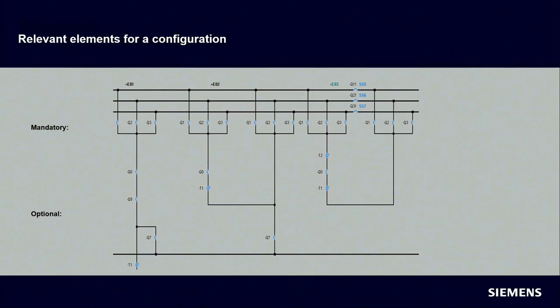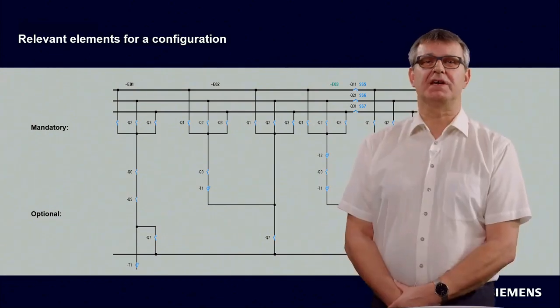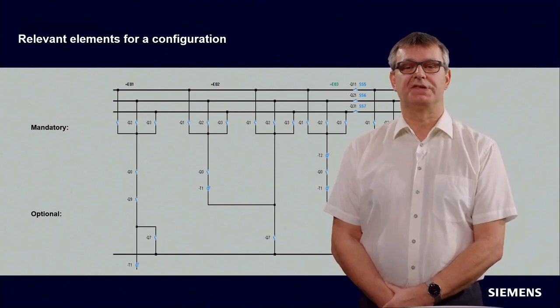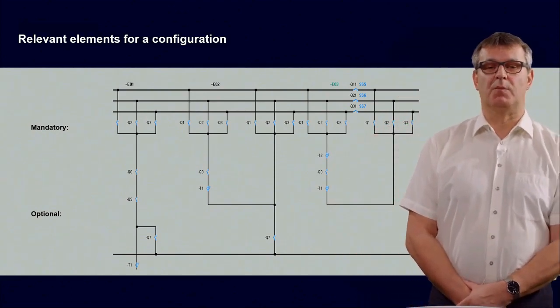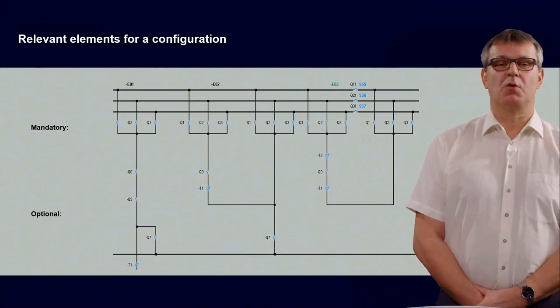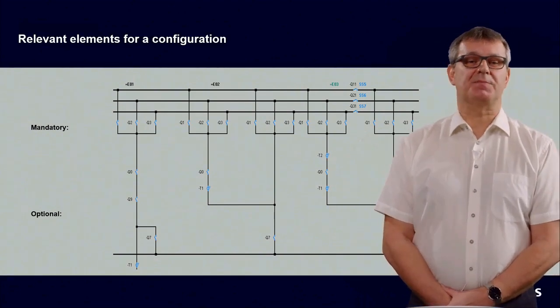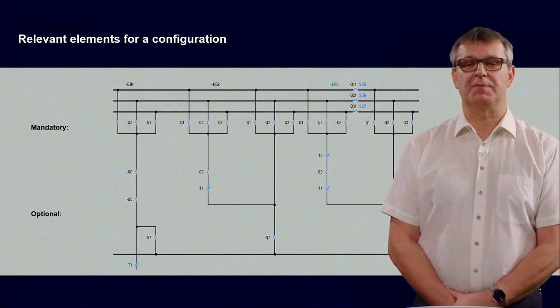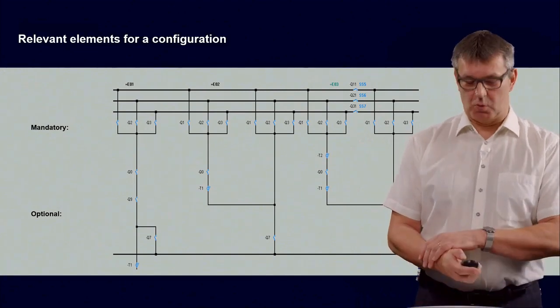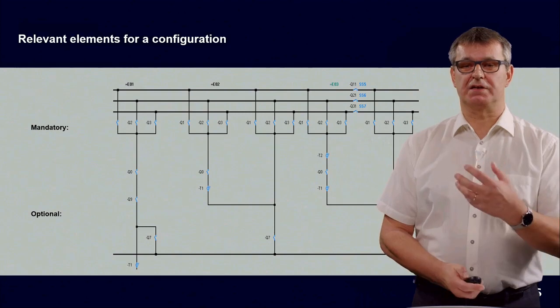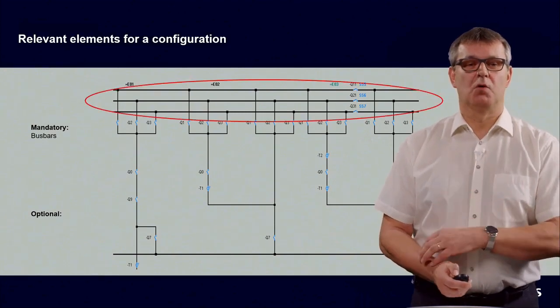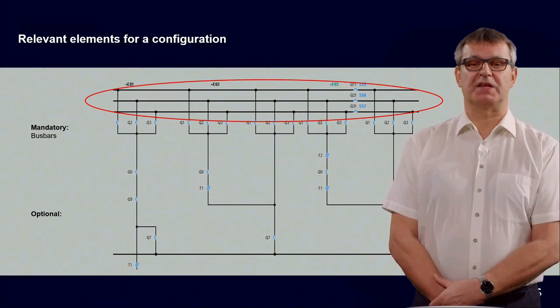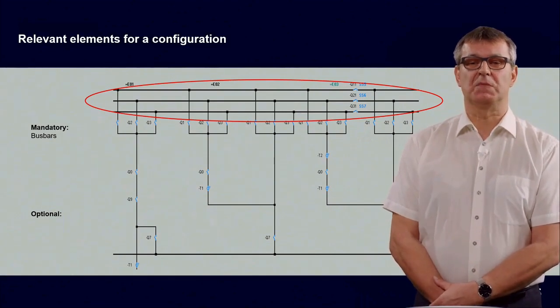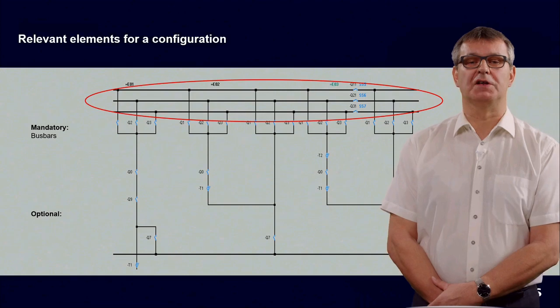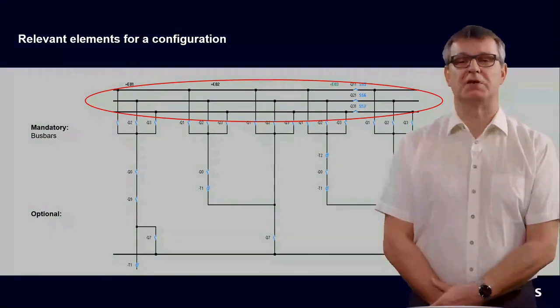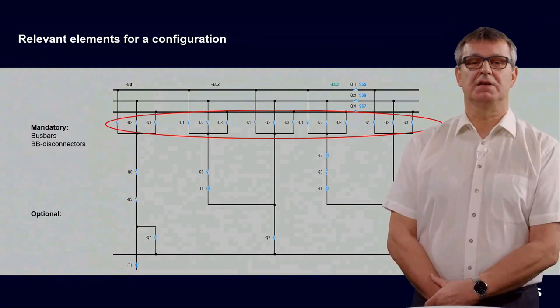What elements do we need to configure busbar protection systems? We see here a more complicated busbar protection system: a triple busbar with also a transfer bus system and one coupler. So what do we need to configure? We need to configure the busbars, shown here. We see all in all 6 busbars, 6 independent measurement systems, busbar sections.